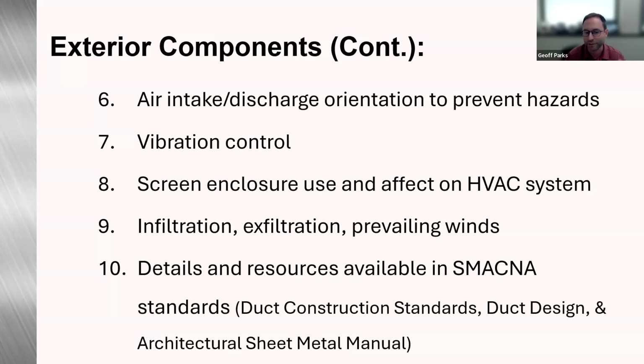That takes us back up to number 6, orienting your air intakes and discharge. You need to know the prevailing winds to make sure you don't discharge something and then have an intake right there that's going to pull it back into the system. And then finally, details and resources are available from SMACNA standards, which would be your Duct Construction Standards, Duct Design Manual, and the Architectural Sheet Metal Manual.